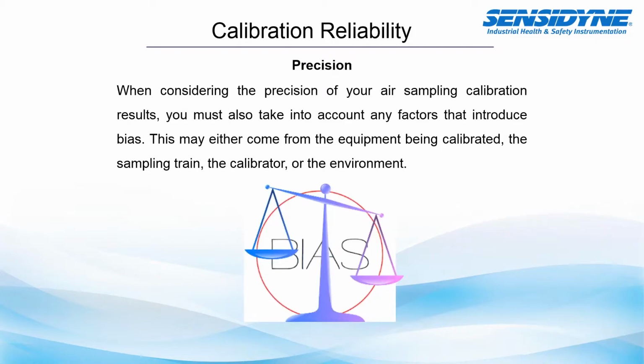Some other things to consider regarding precision. When considering precision of your air sampling calibration, you must also take into account any factors that could introduce bias to your sampling flow rate. This may either come from equipment being calibrated, the sampling train, the calibrator, or the environment in which you might be calibrating.